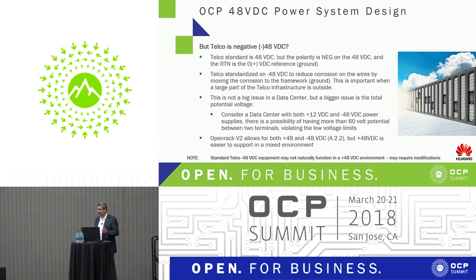If you were to standardize on negative 48 volts, you could have a potential of 60 volts between two bus bars, and that could violate your low voltage limit. So the standard allows the power supply to be plus or minus 48 volts, but it's more logical to stay with a plus 48 volt system.